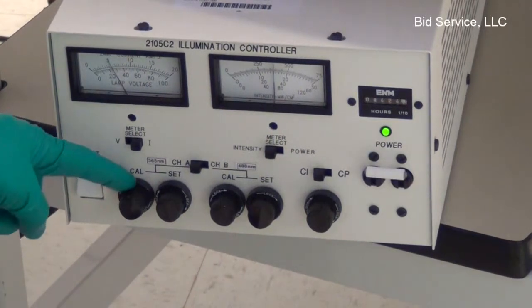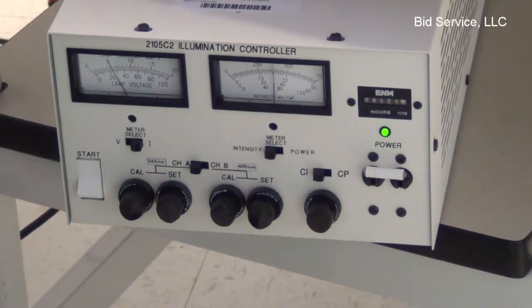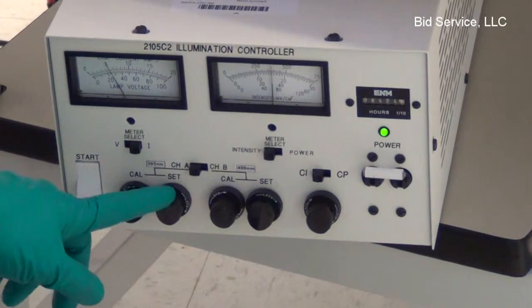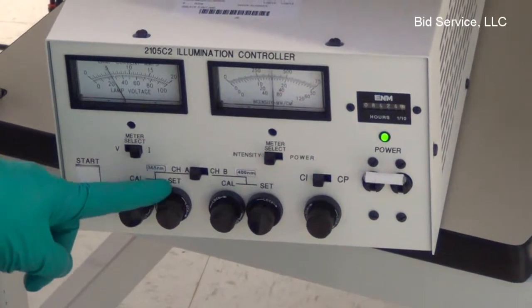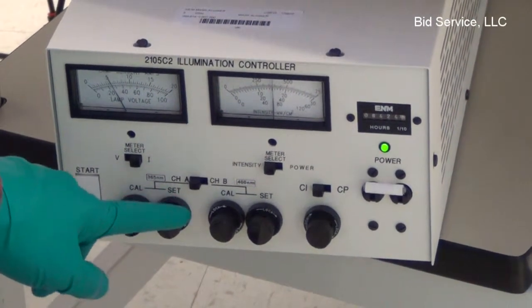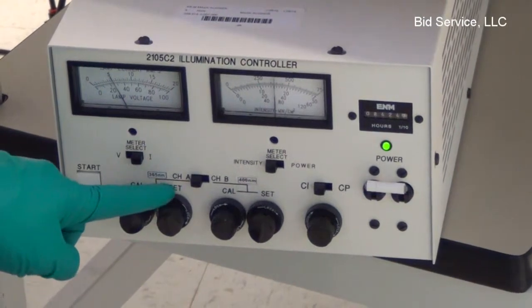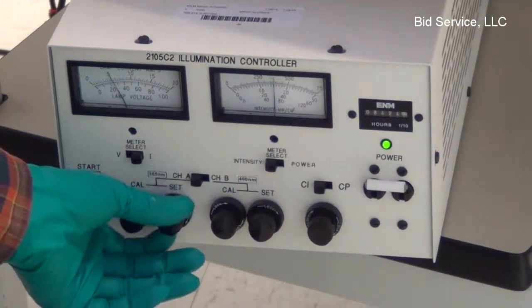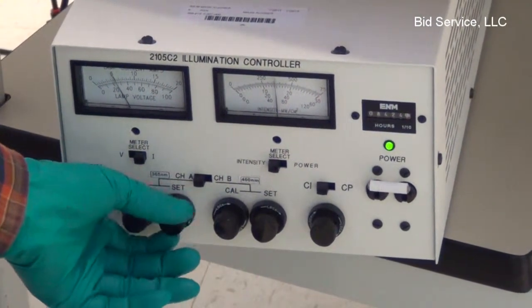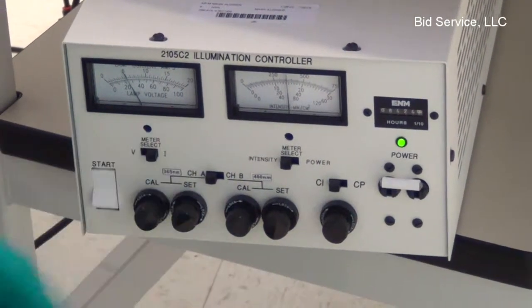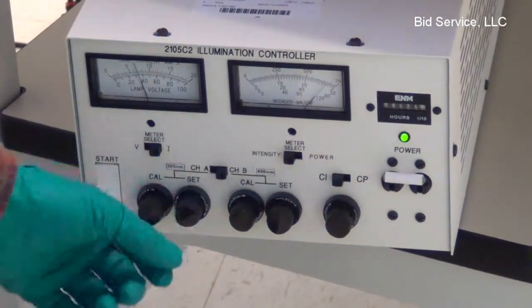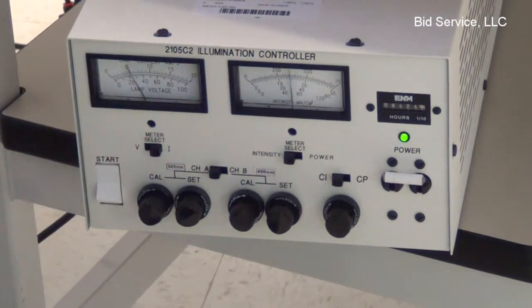By adjusting the calibration at about 450 watt, we can set the power level up to 550 watts maximum, and the lower value could be as low as 400 watts. Similarly, the channel B can be adjusted.